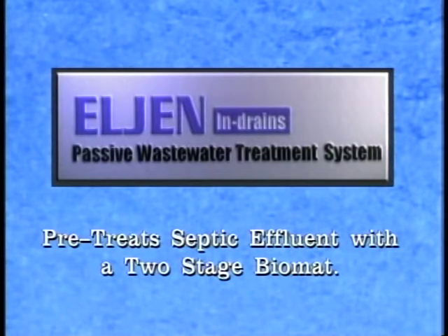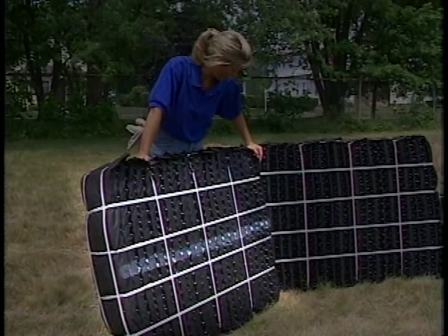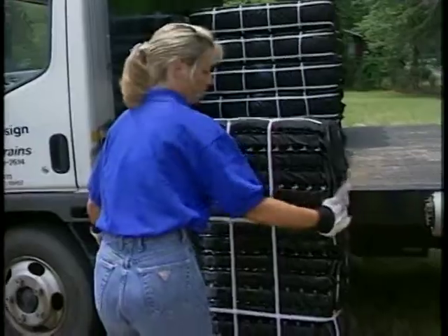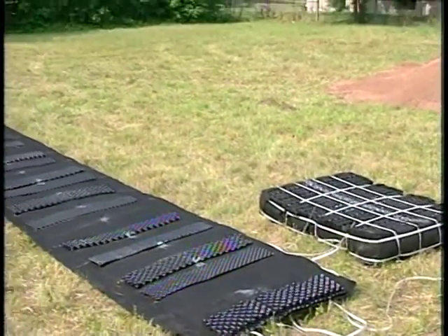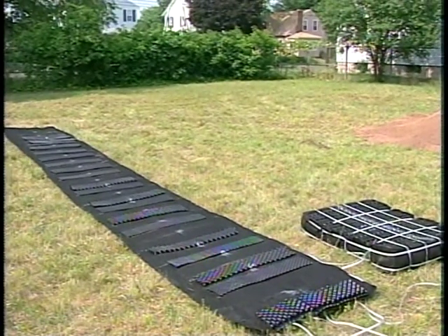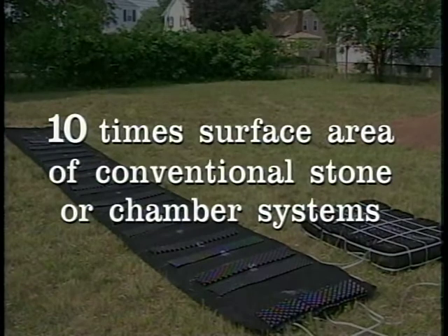The Eljen In-drain treatment system is the only system that pre-treats septic effluent with a two-stage biomat. Constructed of lightweight recycled materials, the finished dimensions of each in-drain unit are 3 feet by 4 feet by 7 inches. With a weight of only 18 pounds, the lightweight construction makes them easy to transport, handle, and install. A continuous length of biofabric is wrapped over and under cuspated core spacers, resulting in approximately 100 square feet of surface area within each in-drain unit. This unique patented design provides up to 10 times the surface area of conventional stone or chamber systems.